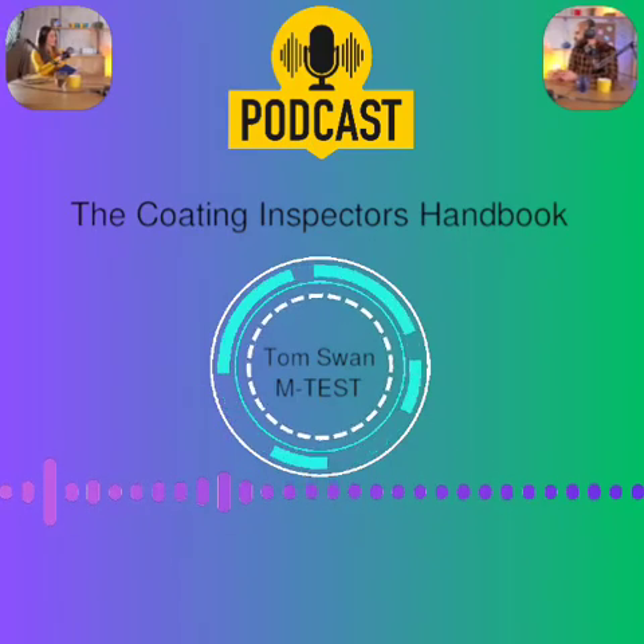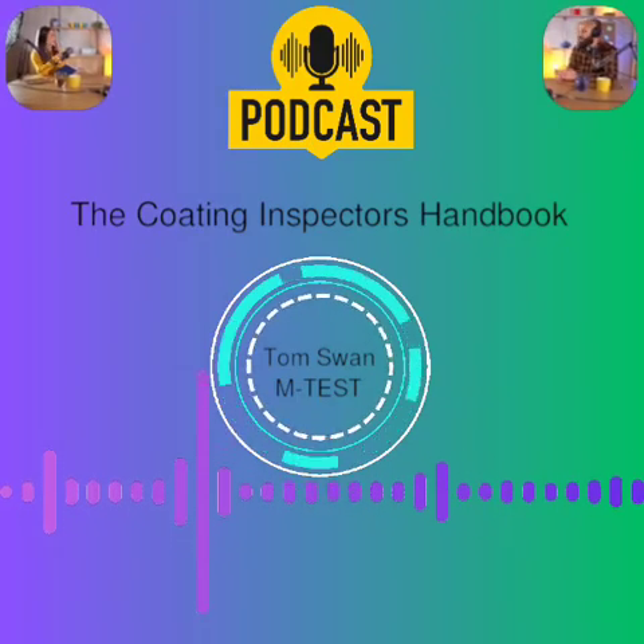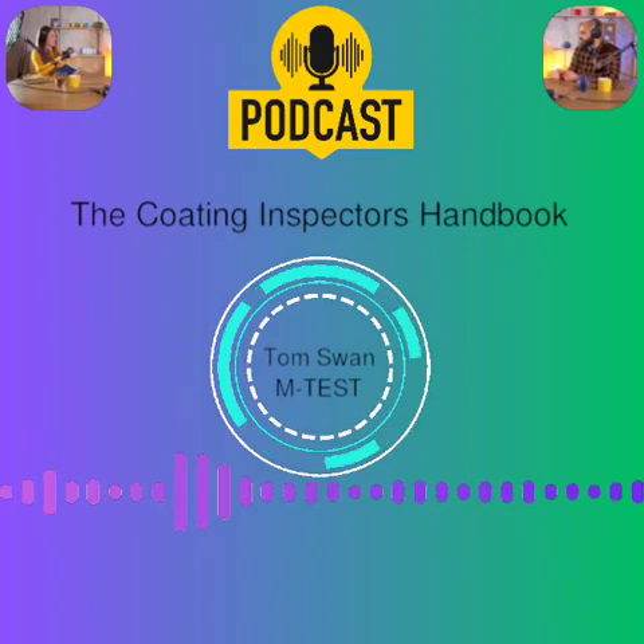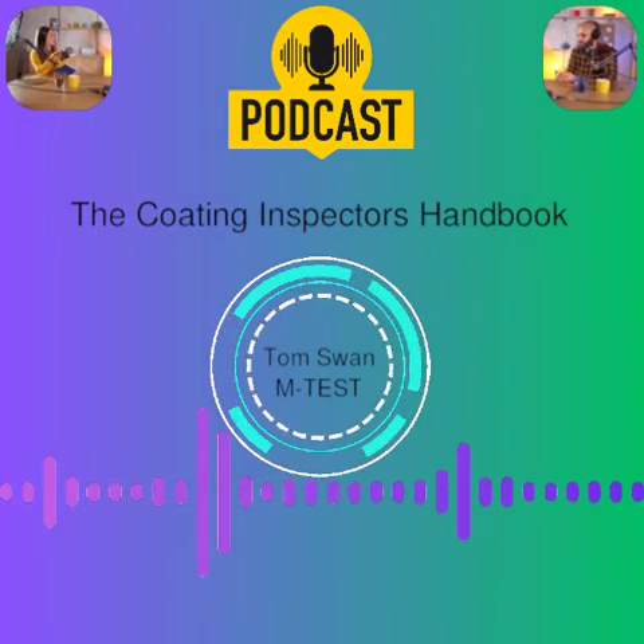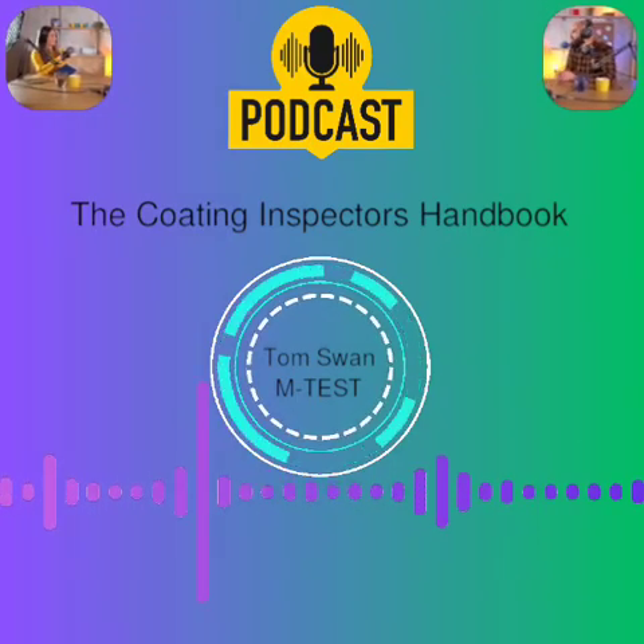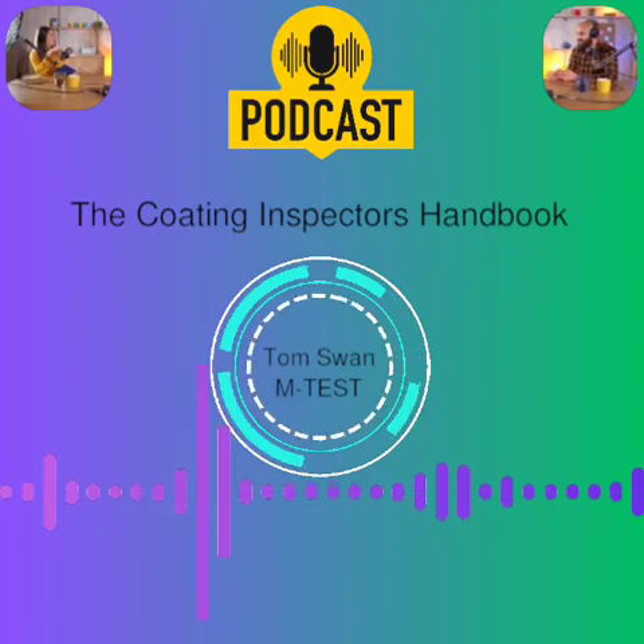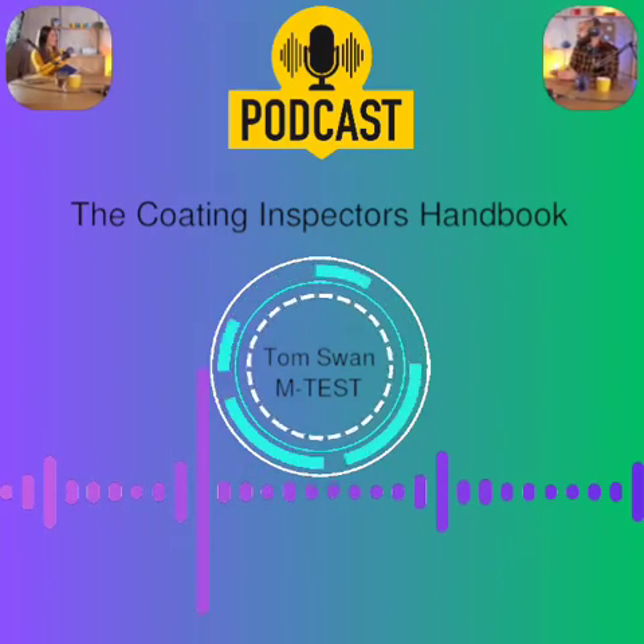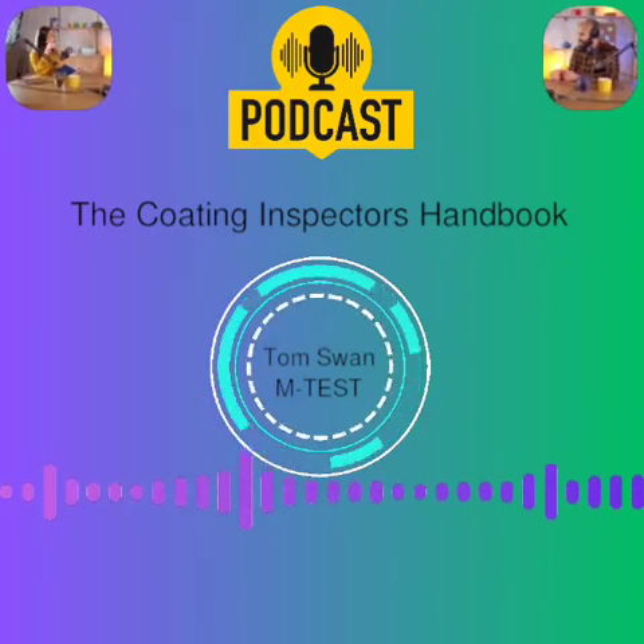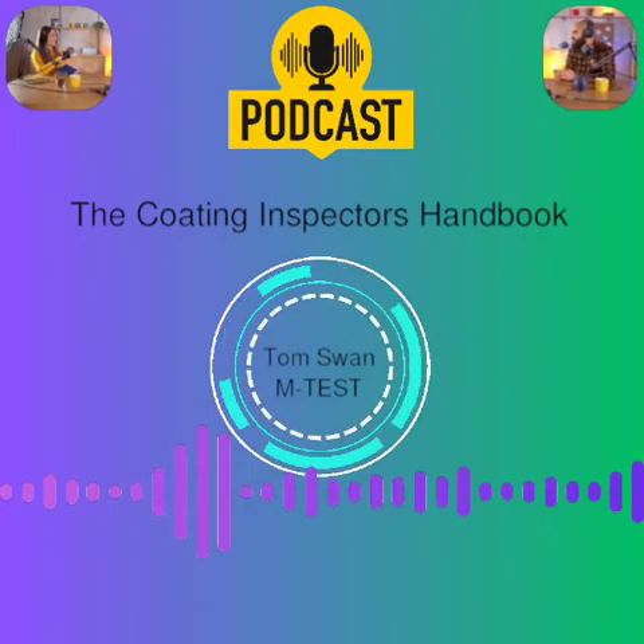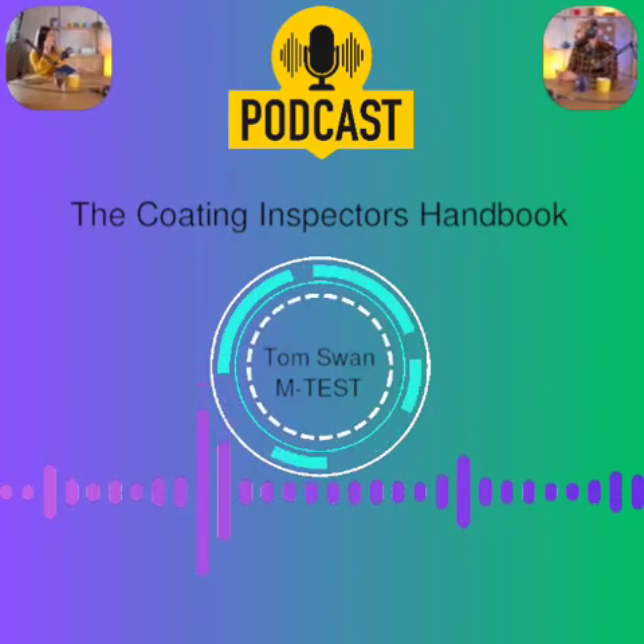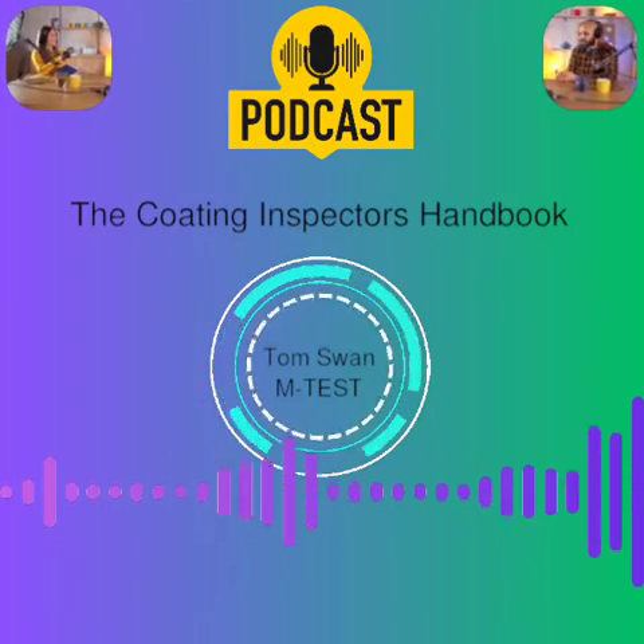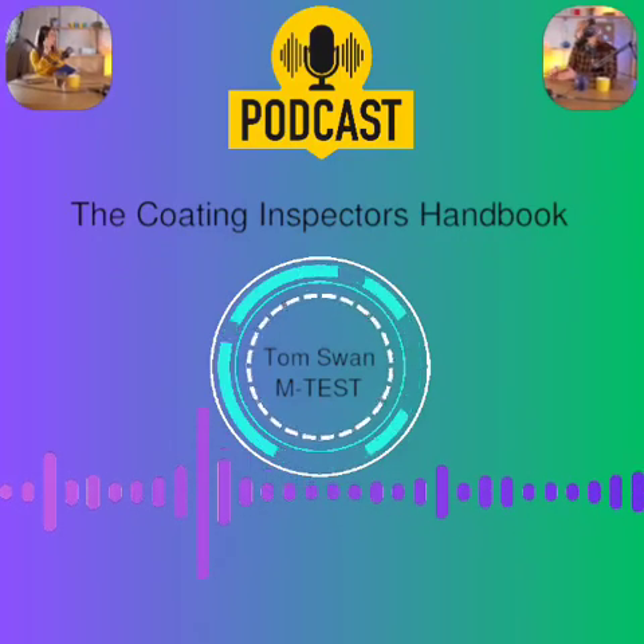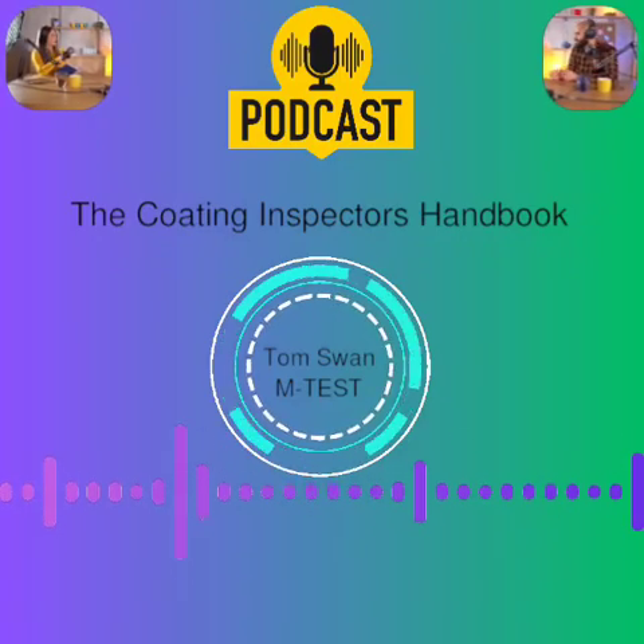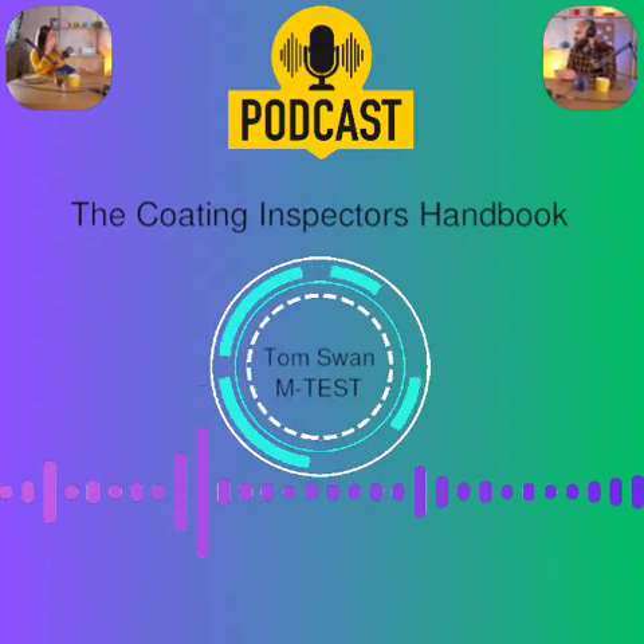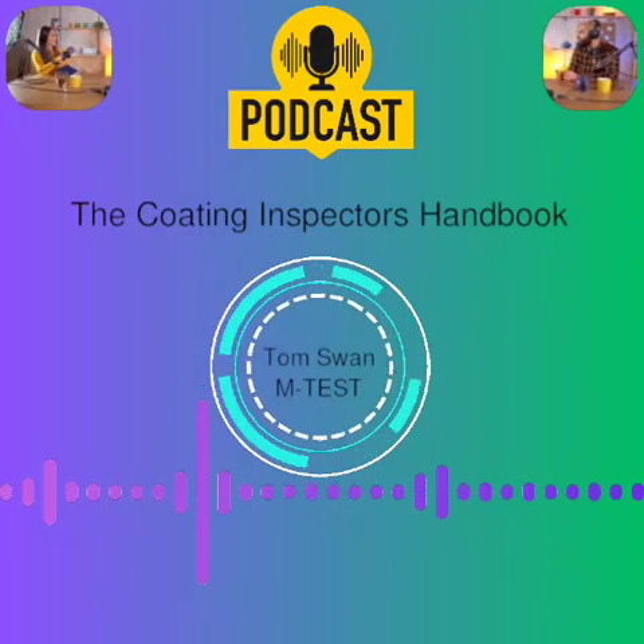What if a spec gives limits in ppm, parts per million? That's usually a red flag. ppm measures concentration in a liquid. A surface limit needs to be amount per area, like micrograms per square centimeter or milligrams per square meter, mg/m². So ppm in a spec is basically meaningless for a surface. Pretty much, unless they also define the exact area tested and the volume of extraction water used, which they rarely do. If you see ppm for a surface limit, you have to go back to the spec writer or owner for clarification before starting. Don't guess.